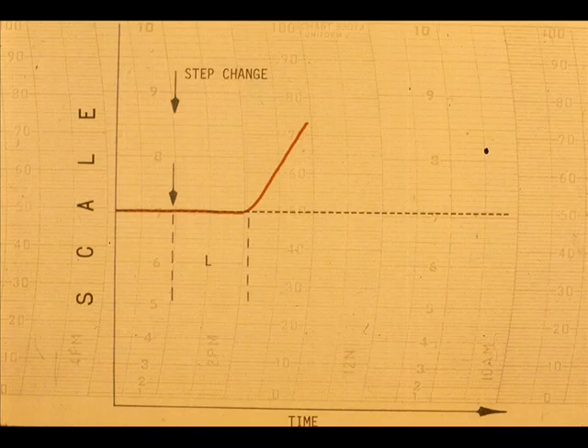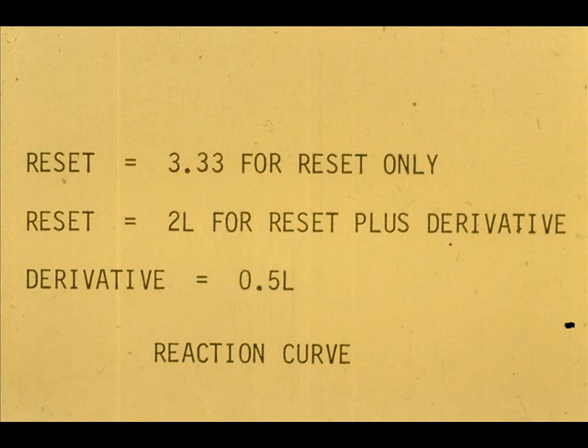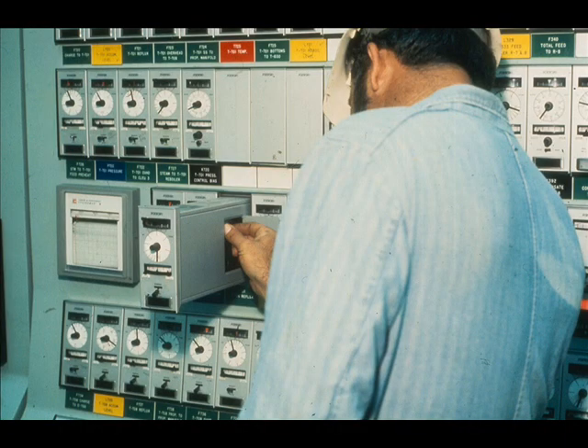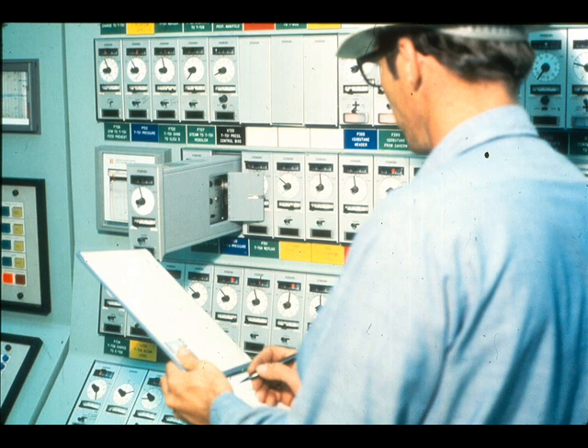The reaction curve tuning method causes the least upset to the process. If we have time to get nothing more than the time for the open-loop response, we can calculate the proper reset and derivative time and adjust accordingly. The open-loop response can be timed reasonably well with an ordinary watch — a stopwatch is better. The proportional band can then be adjusted experimentally with the controller back in service. Once proper tuning adjustments are determined, record them for future use.